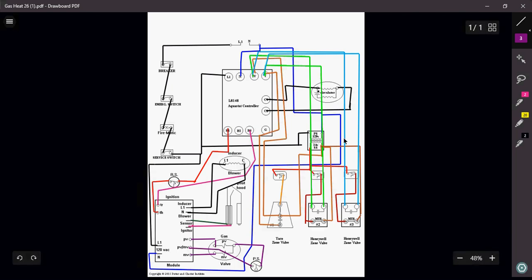This is a little bit more than what you might actually think, but in a nutshell, it is still relatively simple in the sequence of operation. It's just a couple more wires that are going on. Really your sequence of operation for this type of system is that you have to have a call for heat from one of your thermostats in one of your zones. Once that thermostat calls for heat, the zone valve is now going to open. Once the zone valve opens, it's going to now send that signal through the end switch up to your TT terminals on the aquastat.